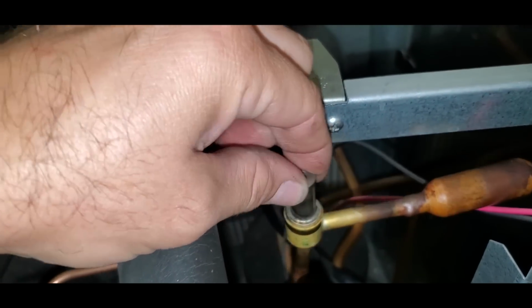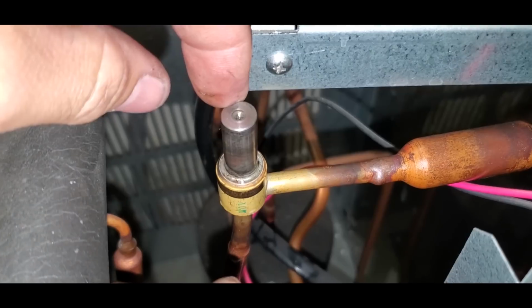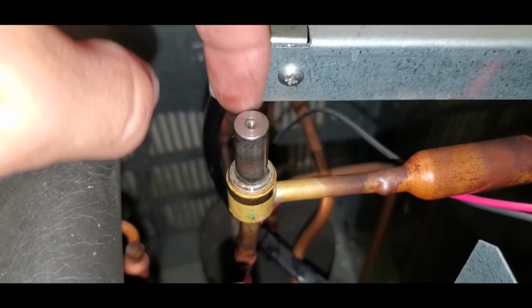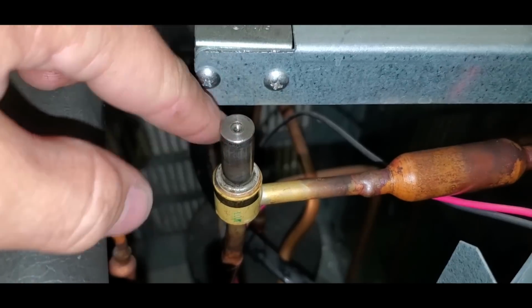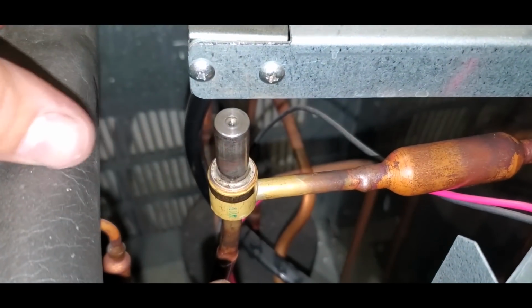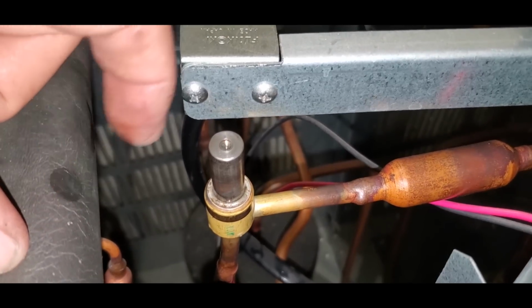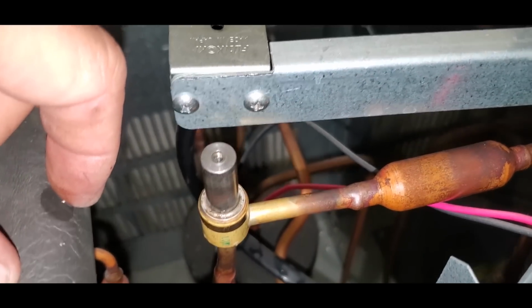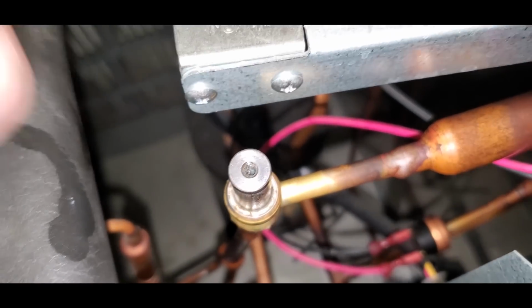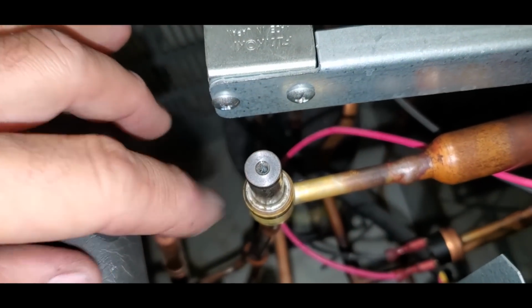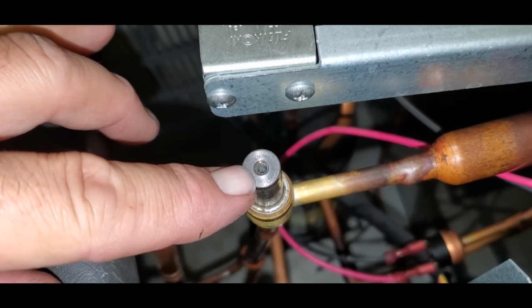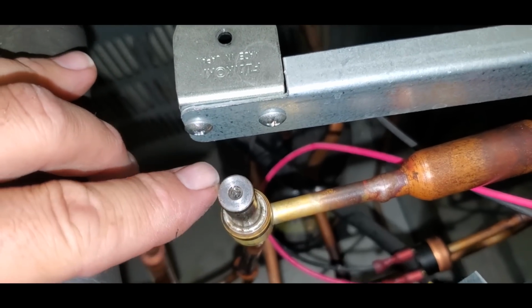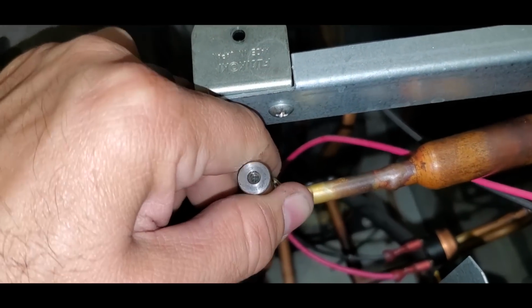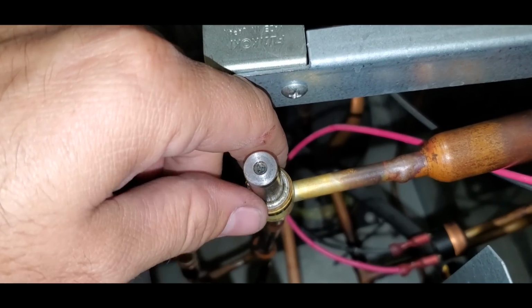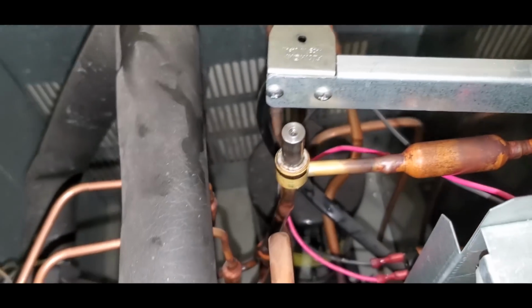I'm trying to move the stem around to see if I can get it to leak. Careful though, the thing will blow off in my face. Ah, there it is. Right in the stem. Popping up. It's this tiny bubble right up here in the stem that just appeared when I moved this. Yep, so I'm pretty confident there's a leak there.